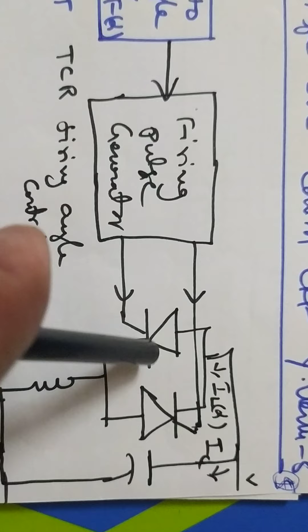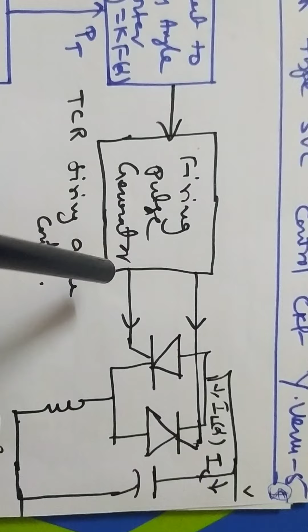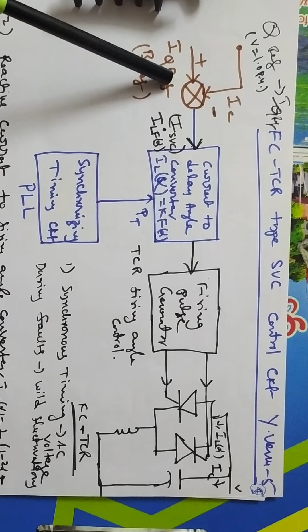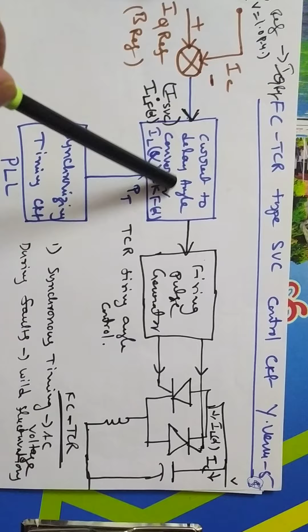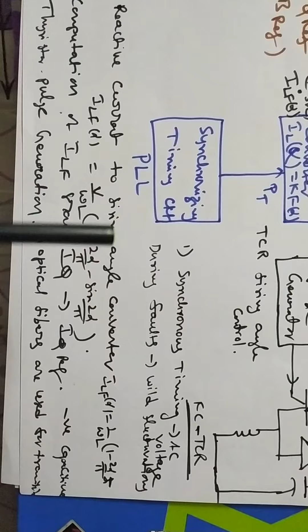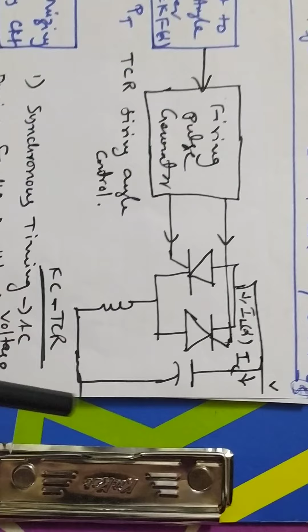So this is another function of your control circuit. This firing pulse generator will generate the pulses and give the signal through optocouplers to the anti-parallel combination of thyristors of the TCR. Like that, we have control over the FC-TCR type SVC. This is the overall control circuit of your FC-TCR type SVC, which comprises the computation of ILF alpha from the IQ reference, generating the synchronizing and timing signal in synchronism with the system voltage, and computation of alpha from the known value of ILF alpha from the relation given in this equation. Then, in synchronism with the system, the firing pulse generator generates the pulses and gives the signal using optical fibers to the anti-parallel combination of thyristors of the TCR. This is the FC-TCR type SVC power circuit, and this is the control circuit.